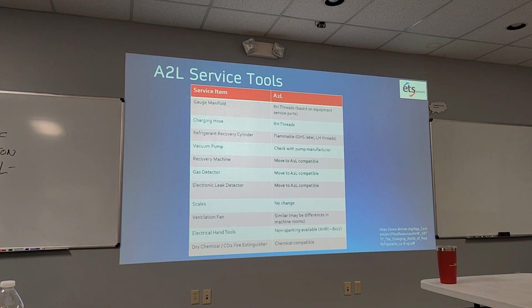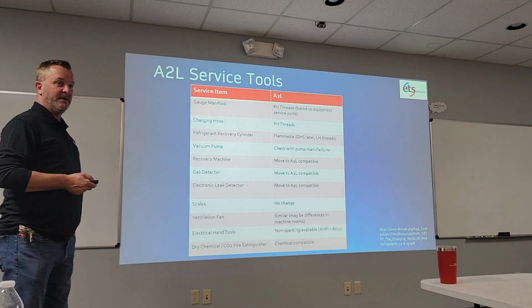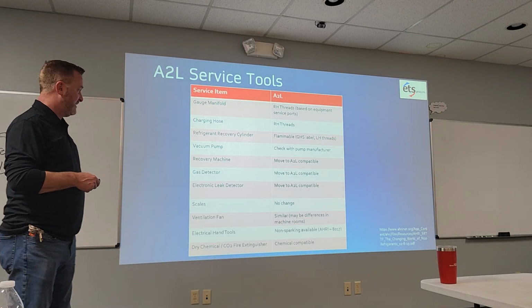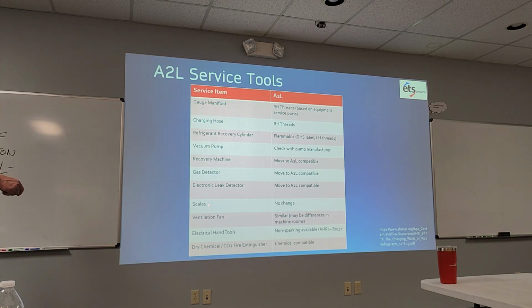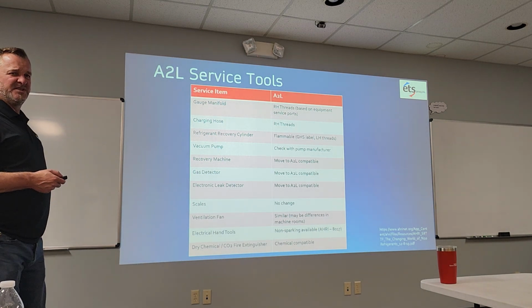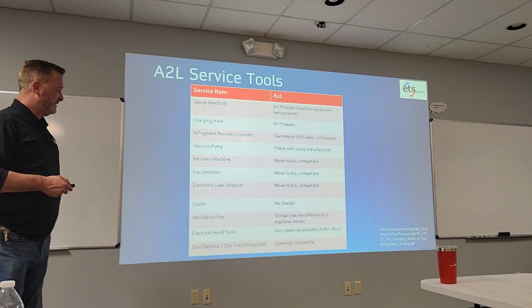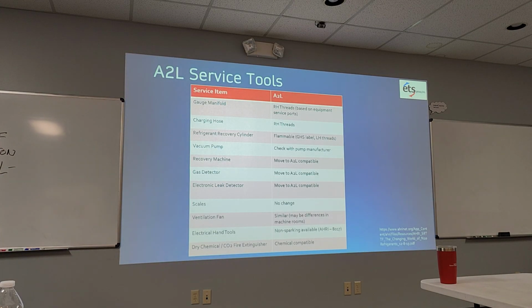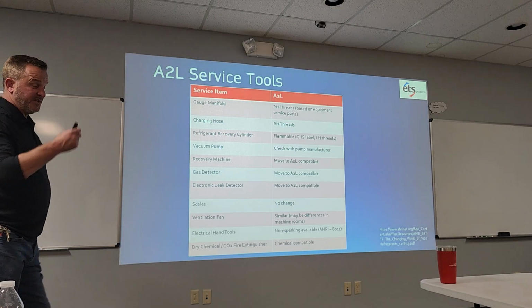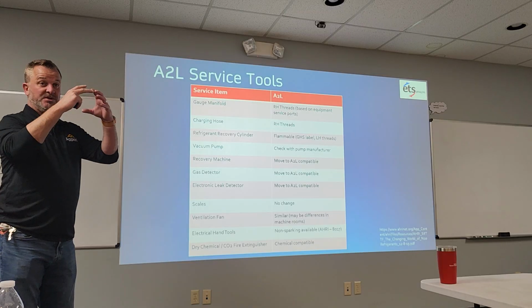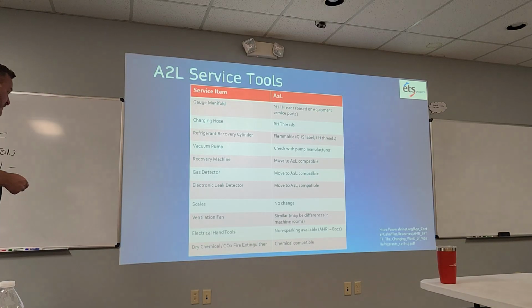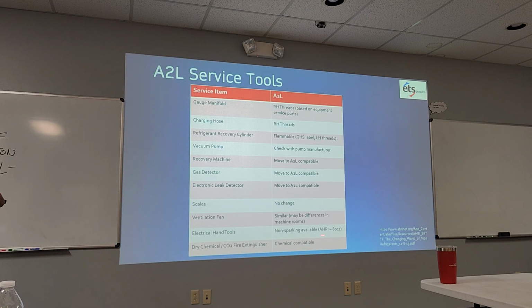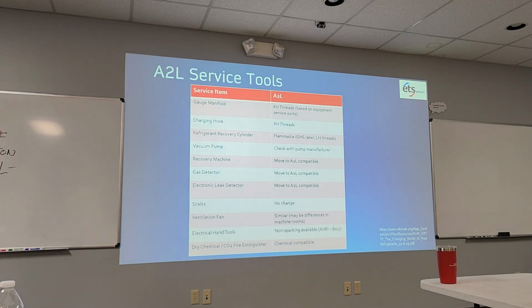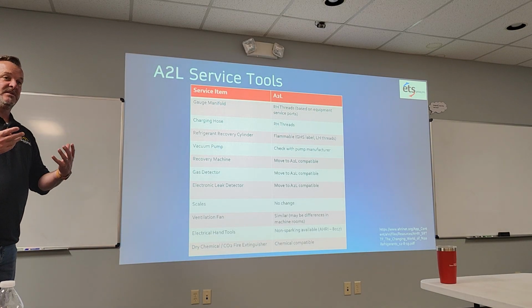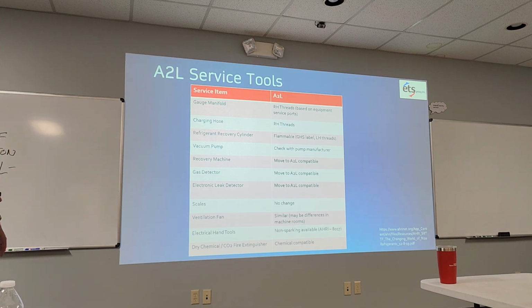Gas leak detectors - you want to make sure those are A2L compatible, and that they're able to find 454B and 32 and things like that. Electronic leak detectors, scales - there's no change there. A lot of these scales are going digital, but it still doesn't really mean much; it's not going to cause any sparks or anything like that. Your ventilation fans are similar, but there may be differences in machine rooms - they have to be bigger, enclosed, and make sure there's no sparking in there. Electrical hand tools, as I said before, need to be non-sparking, so they have to be intrinsically safe. So when you're out there buying a multimeter or other things you wouldn't even consider with refrigerant, make sure they're A2L approved as well.